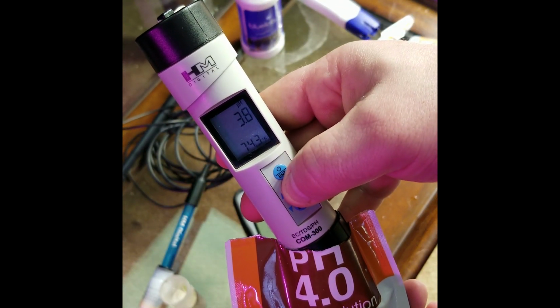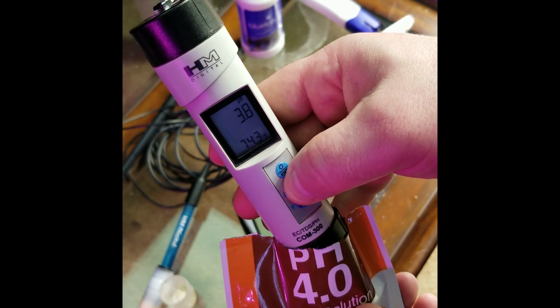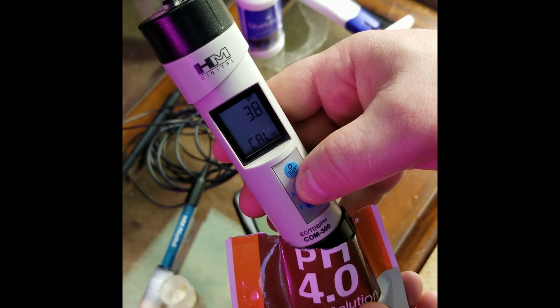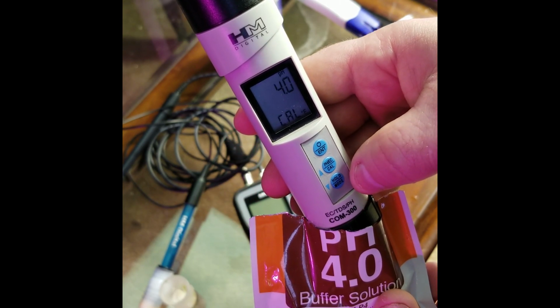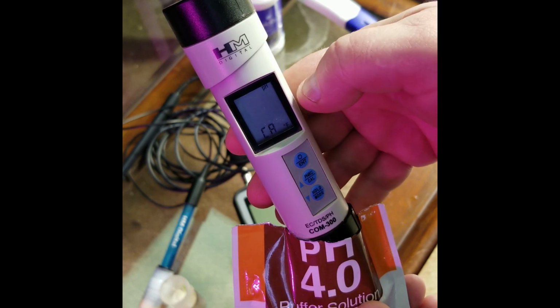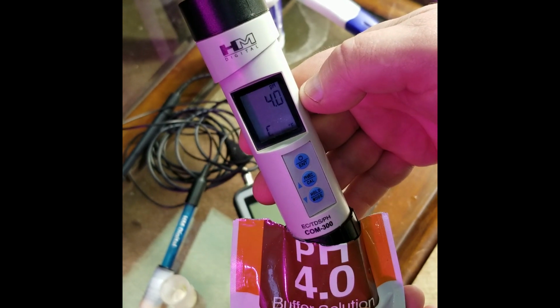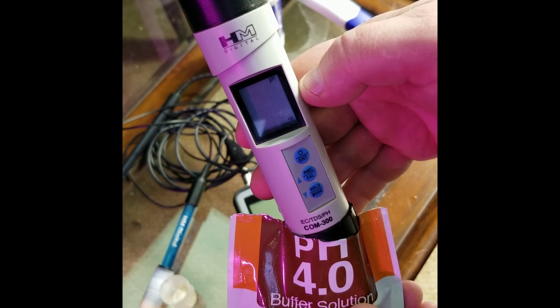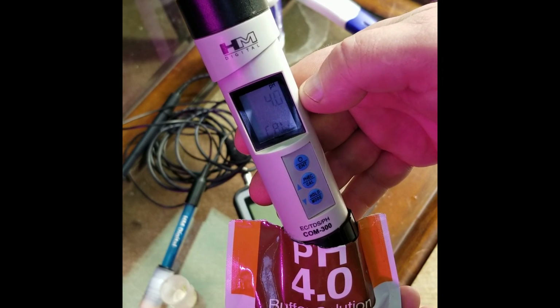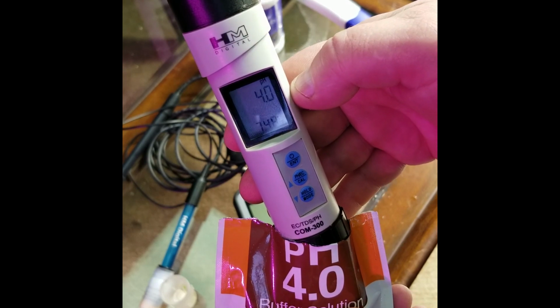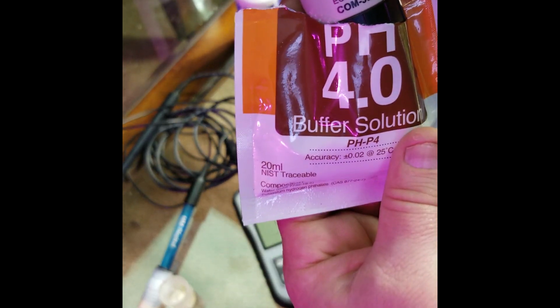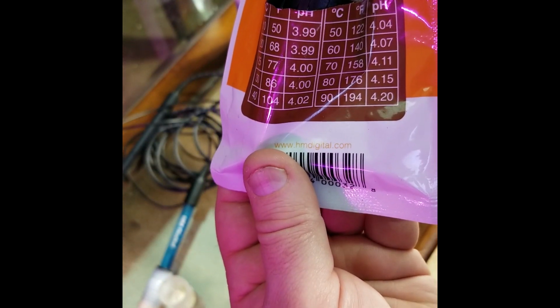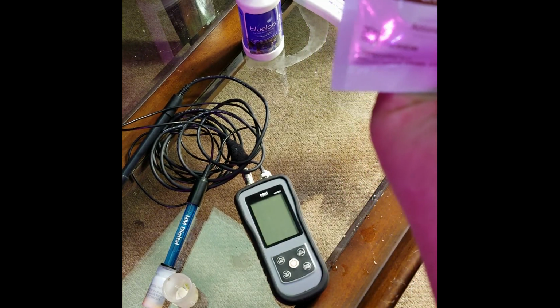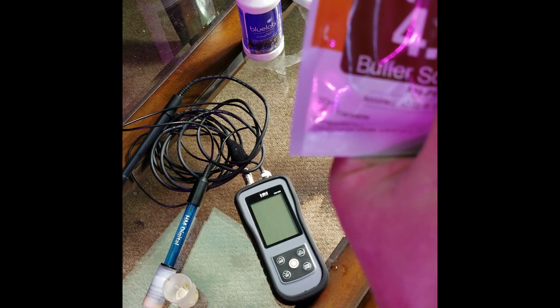So I'm going to press and hold the cal button. That brings up my calibration. It starts flashing. I'm going to up arrow to 4, and then I'm going to hit enter, and it's going to do its little thing. Make sure it doesn't shift again. If it does shift, it'll throw an error. You just do it again. And that time it just popped right back to 4. 74 degrees on that. 70, 68, 77, 3.99 to 4.0. Right on the money. So I'm good enough with that, and I'm ready to go.